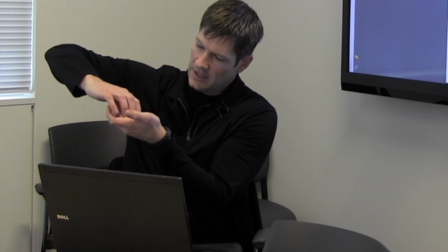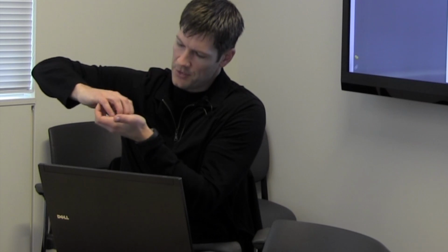And really it's a scroll compressor, so your scroll compressor's spinning like this, compressing the refrigerant down to the middle, right? It's like two spirals going together, and it compresses the refrigerant down to the middle. And it's a stator and a rotor, and they're operating like that. And what it does is it actually relieves pressure on the top to lift this up just 1/8 of an inch. And when it does that, it still spins. The motor's still running, and you will hear this difference. It's loud, and then it gets quieter, but it's on the whole time.